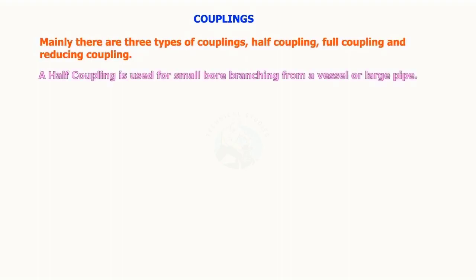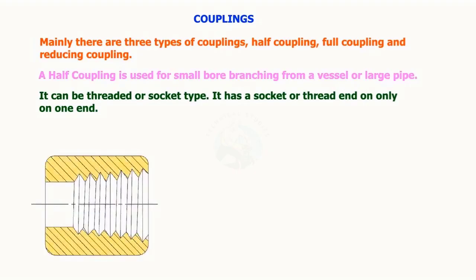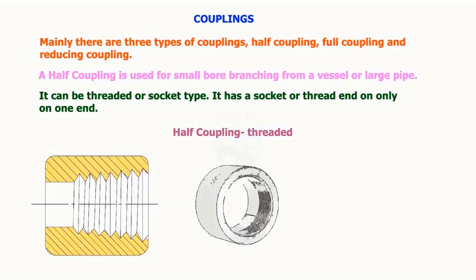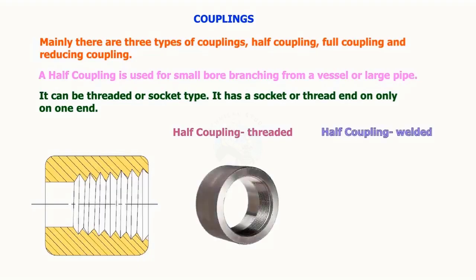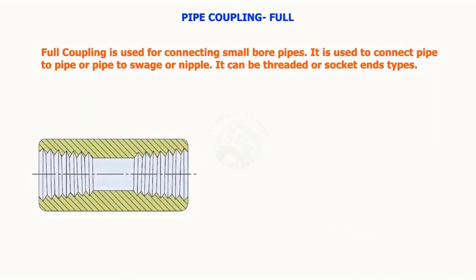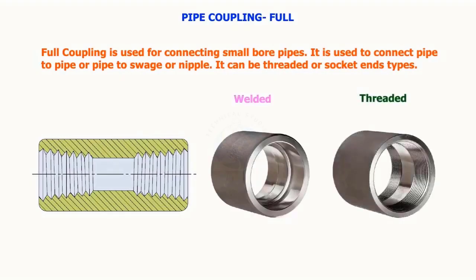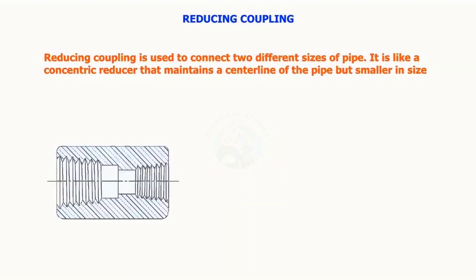Mainly there are three types of couplings: half coupling, full coupling, and reducing coupling. A half coupling is used for small bore branching from a vessel or a large pipe. It can be threaded or socket type, with a socket or thread end only on one end. Full coupling is used for connecting small bore pipes, to connect pipe to pipe or pipe to swage or nipple. Reducing coupling is used to connect two different sizes of pipes; it is like a concentric reducer that maintains the centerline of the pipe but is smaller in size.